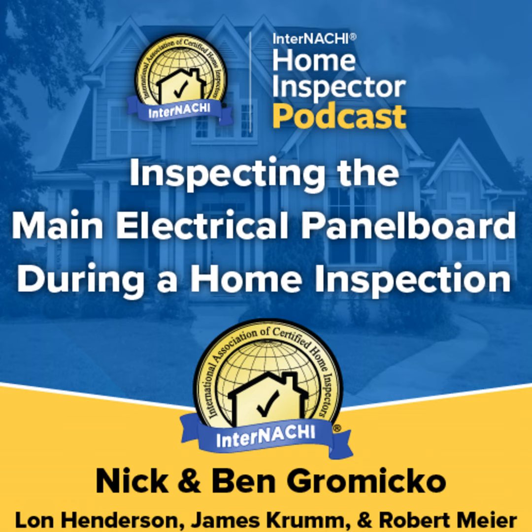White powder. A white powder may be observed on breakers, and this is usually observed in older panels. Some manufacturers of these breakers have explained that the white powdery residue is from a plug used in the manufacturing process that breaks down. It's a material used to keep someone from tampering with the screw. Keep in mind, it's not always white. The manufacturers claim that it is not an indicator of defective breakers and that the breakers are not damaged by it.